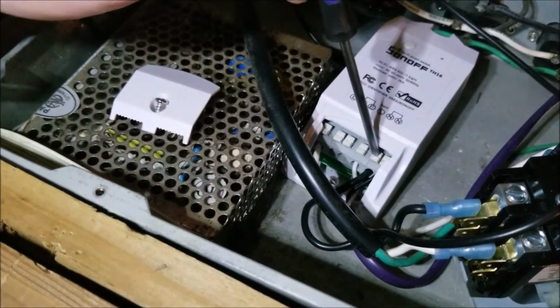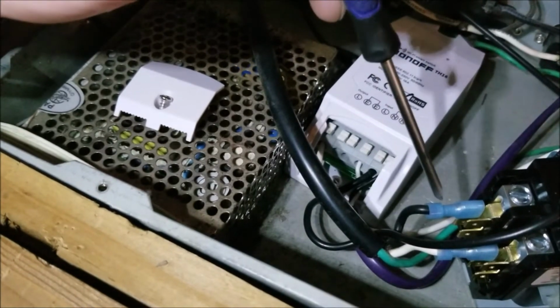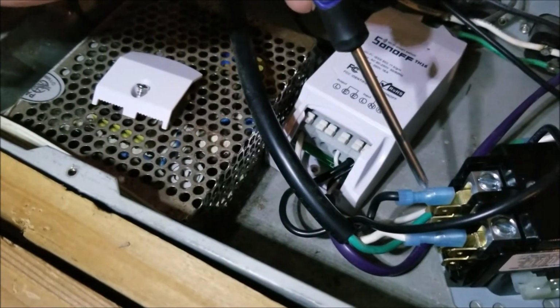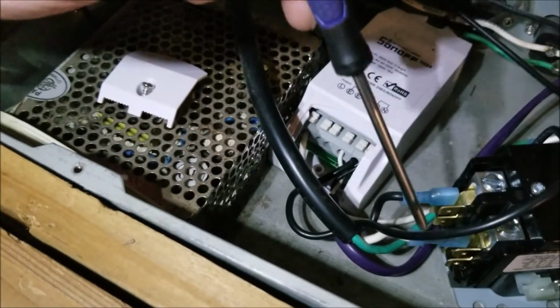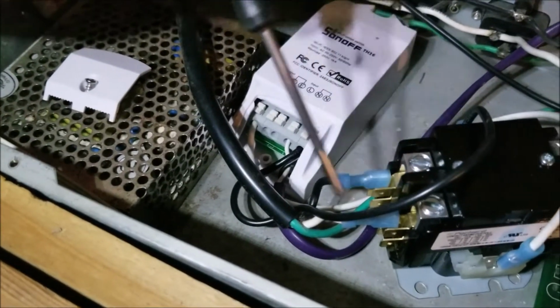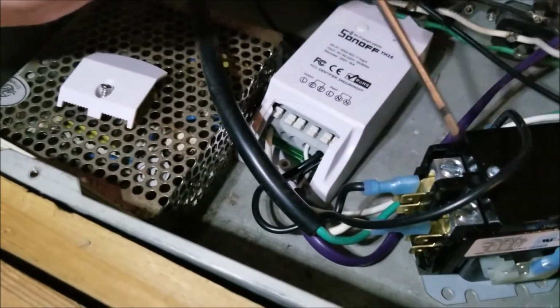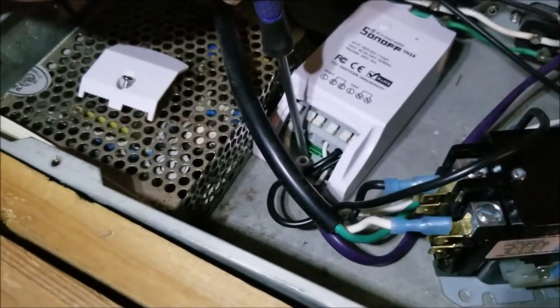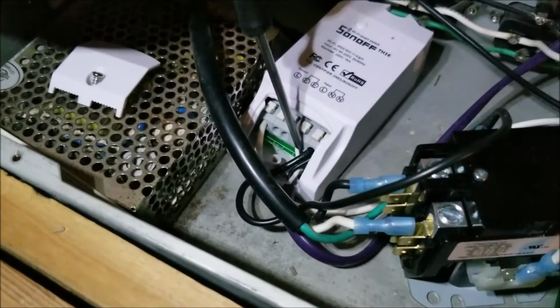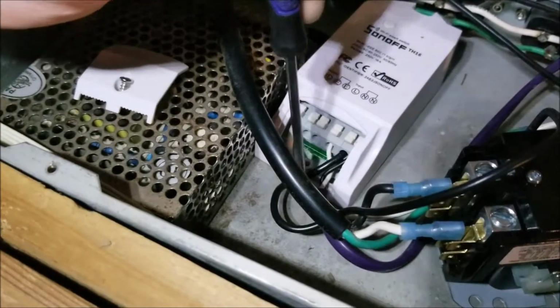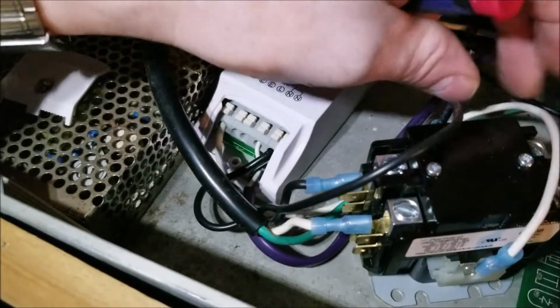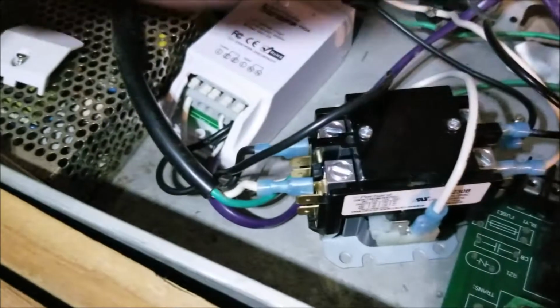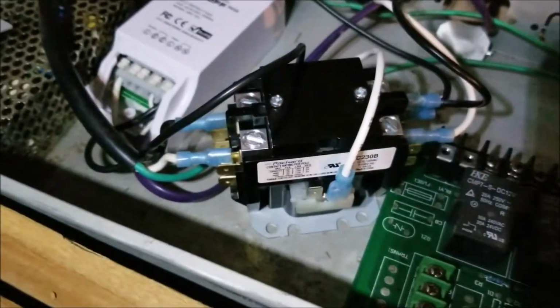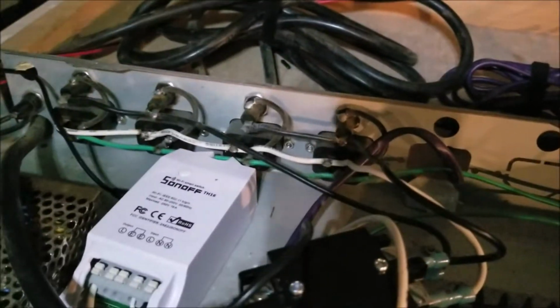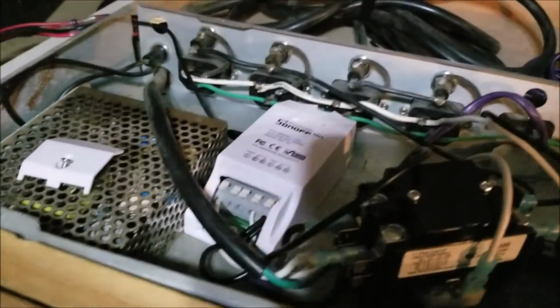And then that wire gets split to your two black wires. One's coming in, one's going out, and that's going to power one side of your relay. The output is going to be your white, which powers the other side of your relay. And then once your relay is engaged by the output wire coming to the other side of the relay, that generates what pulls the contact together that lets the voltage flow to your whole sauna unit. So hopefully that ends some of the confusion on how that works, and it works pretty flawlessly too.